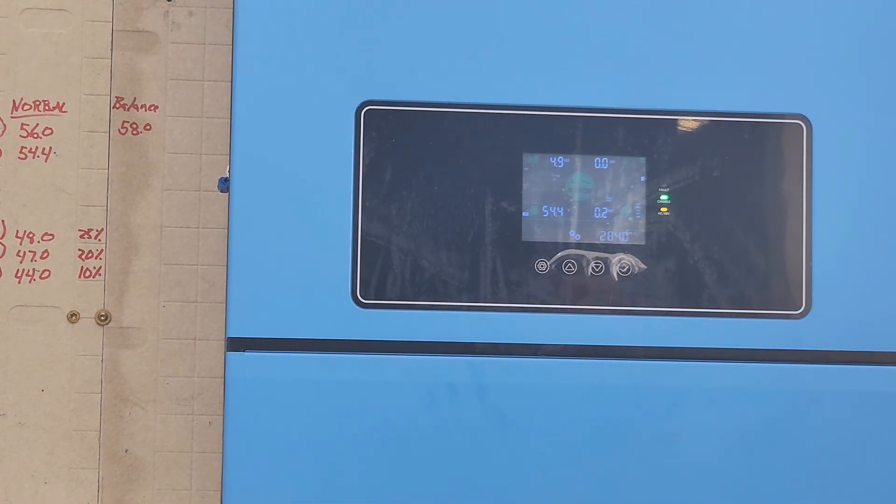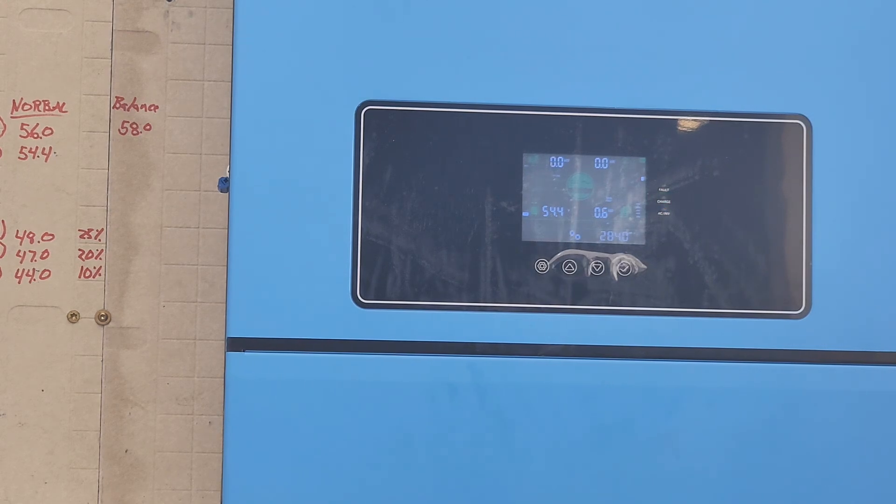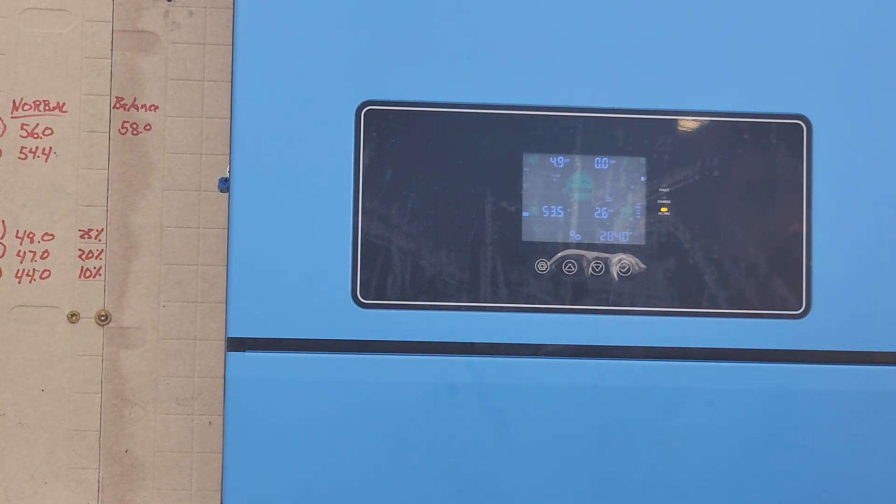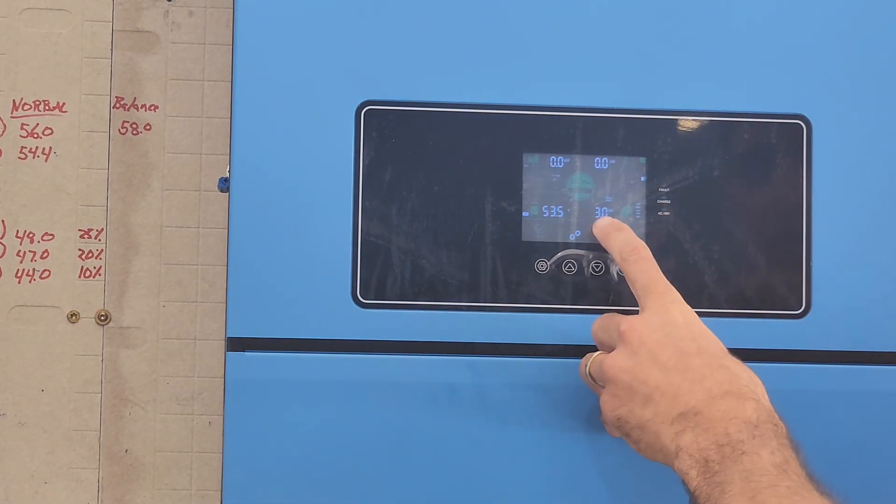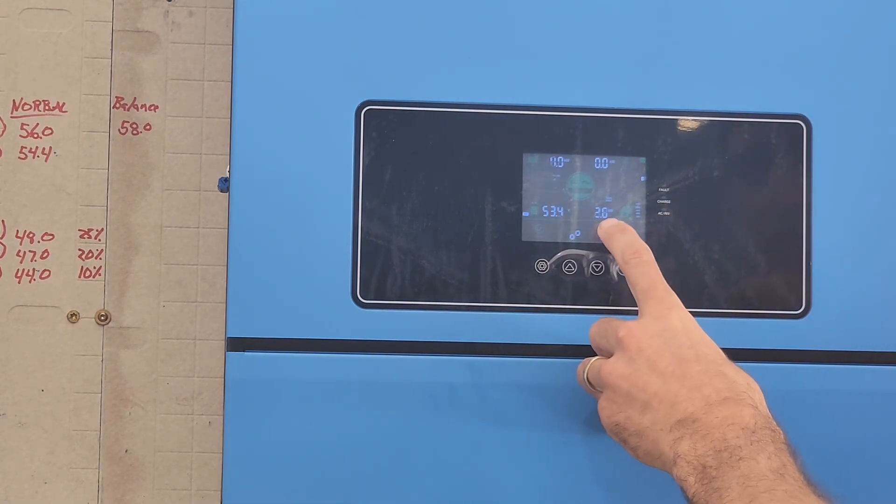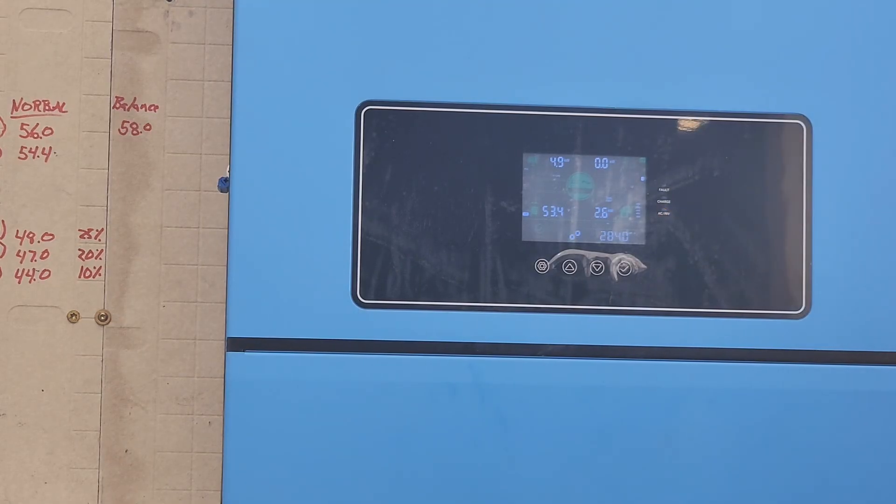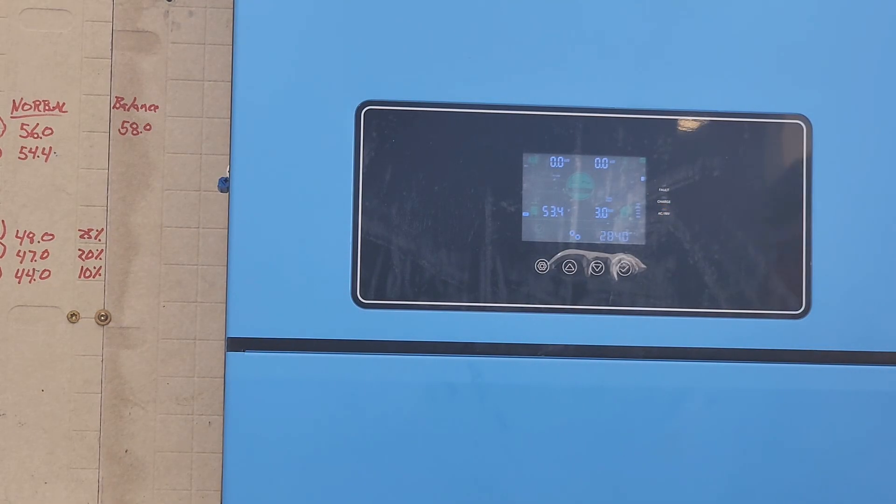First thing I'm going to hit is the hot water heater. That's going to kick it up quite a bit. So now we have 3 on one leg and 2.6 on another leg. Let's turn off the hot water heater and I'm going to turn on the dryer. I think we're going to get a lot closer to what our max is with that.